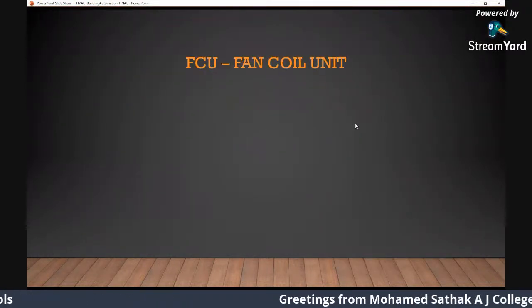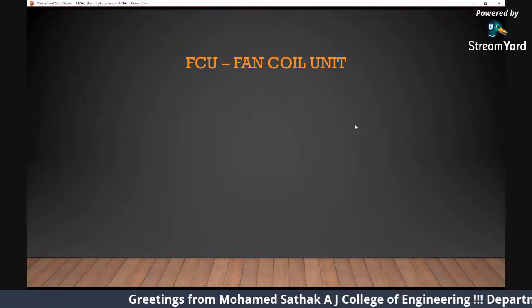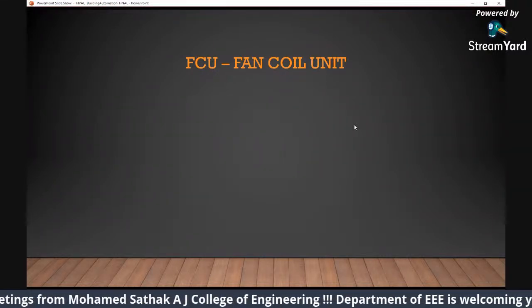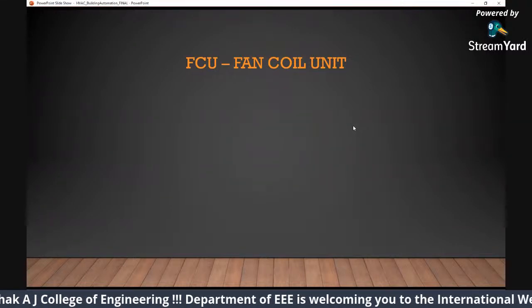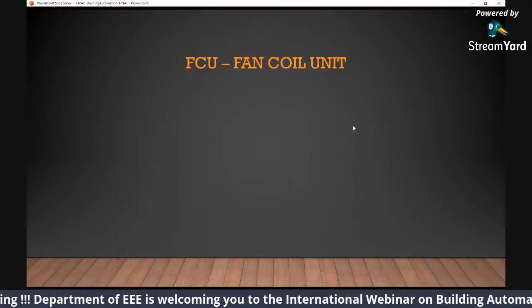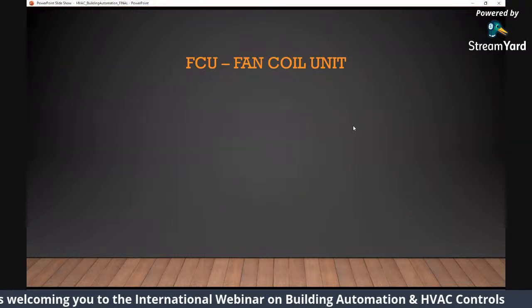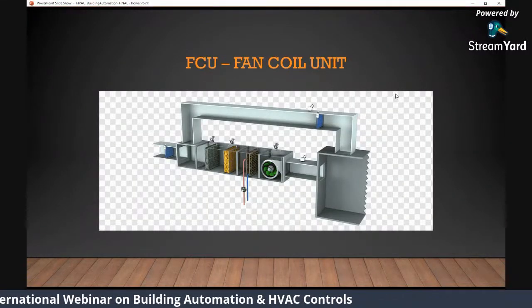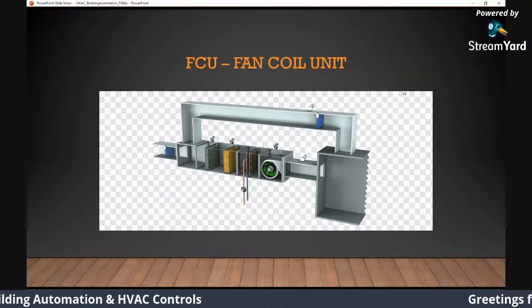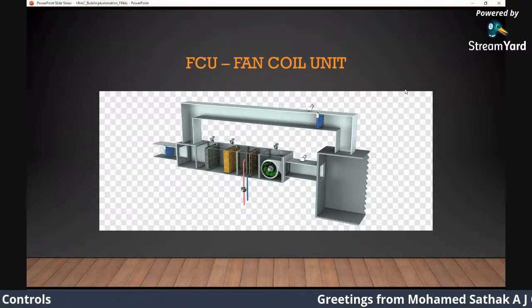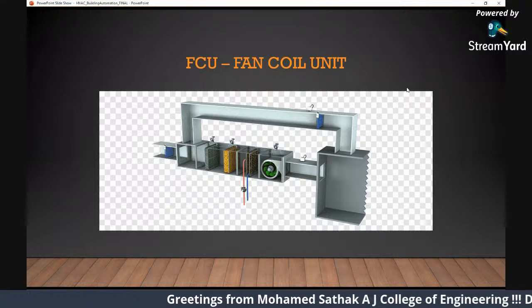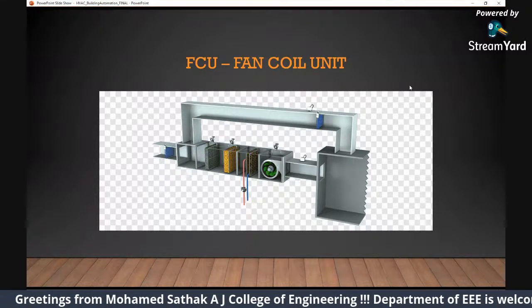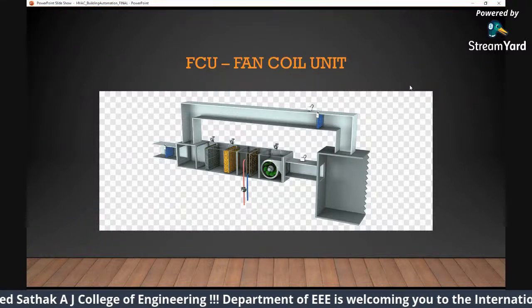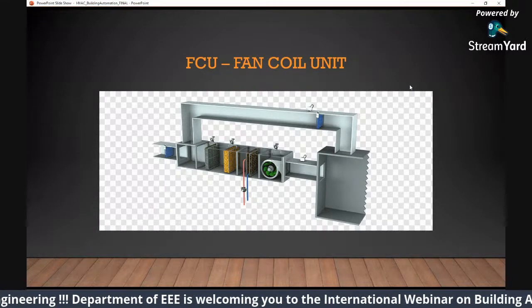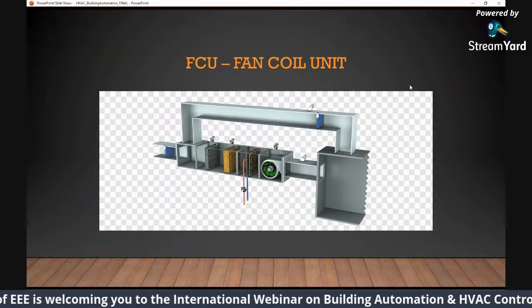So yeah, that's the complete concept about the chiller and boiler, the major equipment of an HVAC system. You need air. For that, you need an AHU. You need cold air. For that you need chilled water, which comes from the chiller. You need hot air. For that, you need hot water, which comes from the boiler. All right. So now I said something else: terminal units. Let's say there's a big system which is consistently supplying air. Now there are small units for each room. Your AHU, boiler and chiller are major equipment mounted in the basement or on top of a building. Now there are small rooms in a building, a conference room, a break room. The AHU cannot supply air into every room.